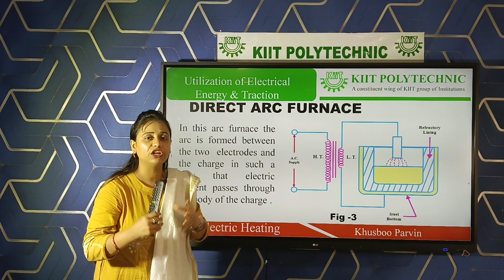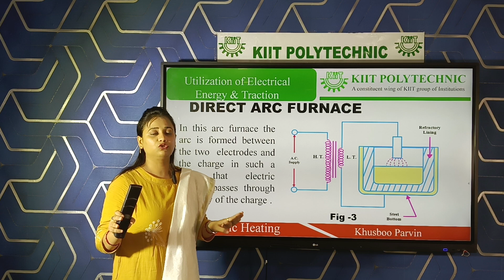This type of furnace is known as a conducting bottom type furnace because the bottom of the furnace is made up of steel. Here you can see one part of the electrode is connected to the secondary winding of a transformer, another part is connected to the bottom of the furnace. When the current flows from the electrode to the base of the furnace, current flows through the charge or the body of the material. As a result, a spark or arc will be produced. That arc or spark comes in contact with the charge, the material which is to be heated, directly. Therefore, this type of arc furnace is known as a direct arc furnace. As a result, the charge of the material which is to be heated gets uniformly heated throughout because of the radiation mode of heat transfer or it might be the conduction mode of heat transfer.